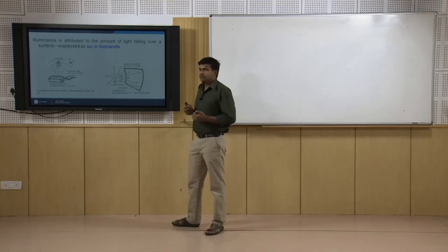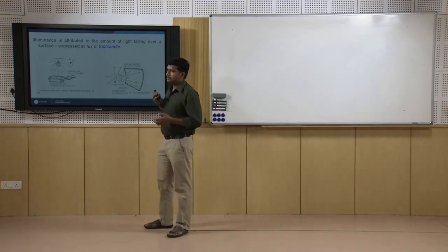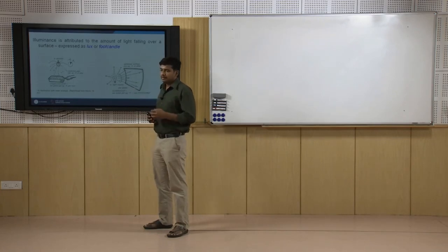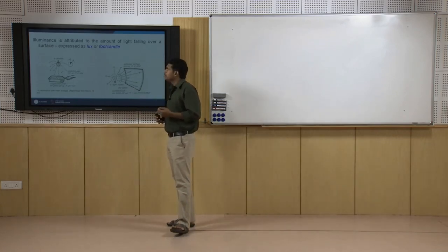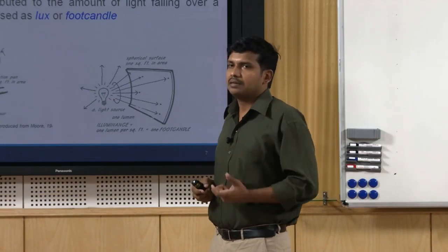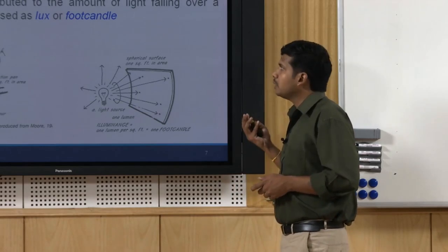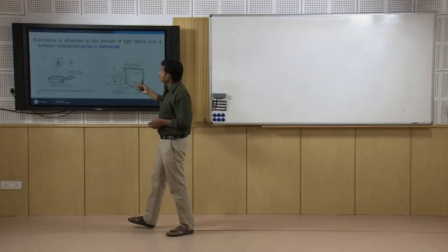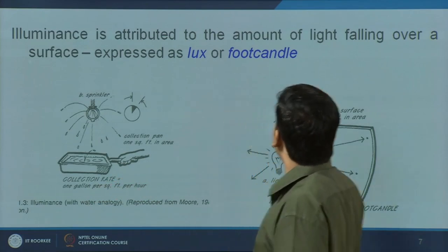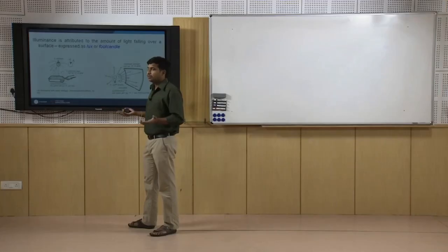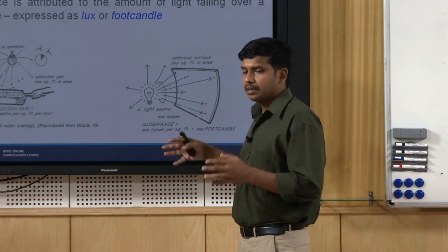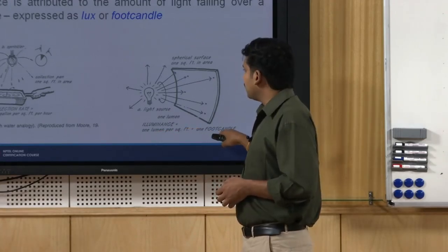Now let us look at two indices which are more commonly used and which standards refer to when specifying the amount or kind of lighting required. The first is illuminance level — you will know this as lux levels. Lux is a unit; in the older system it was called foot candle. It is the amount of light falling over a surface — lumens per square meter or lumens per square feet. One foot candle converts to around 10.8 lux.